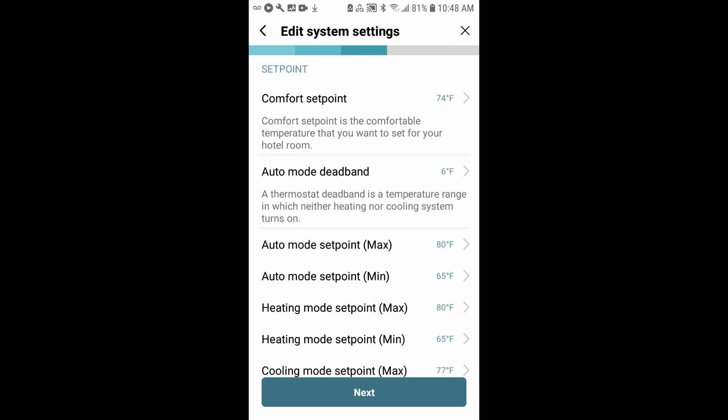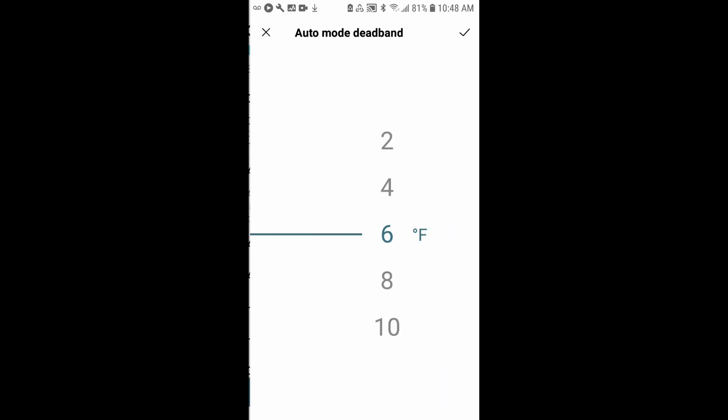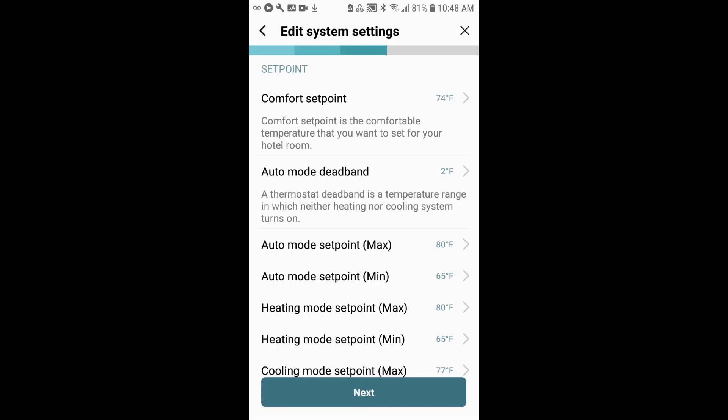For auto mode deadband, this is the temperature range in auto. Whenever it's set to auto mode, neither the heat nor the cooling will turn on. If the auto deadband is set to 6 degrees, that means in auto mode, it will not change to cool until the room hits 77 degrees. I typically like to adjust the auto mode deadband down to 2 or 4 degrees. That means 2 degrees would be 1 degree above or 1 degree below the target temperature. So I'll set that to 2.